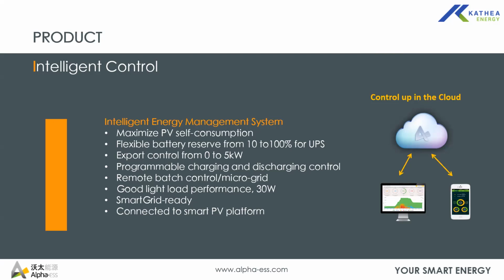If you have an upcoming load shedding and your battery is quite low, then you can quickly log into your monitoring account. Just set your time. It gives two timelines to set. You can set it to charge for the specific time zones. Then it will use grid to charge your battery to a programmable percentage. If you want it charged to full, you can set the battery to charge to 100%. If not, you can set it to any percentage.